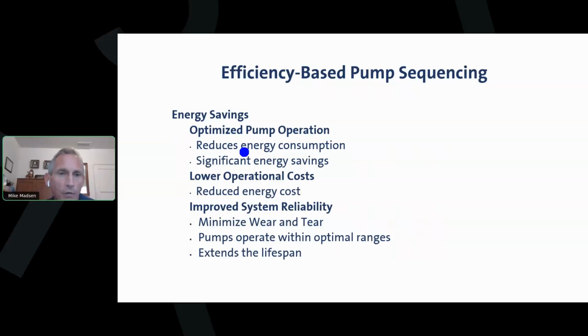So we're going to reduce our overall energy consumption. We're going to rack up significant energy savings and lower our total operating cost. Sort of a side benefit is that as we're running the pumps at slower speed, there's less wear and tear on the equipment also. Running 2 pumps at a slower speed is going to cause less wear and tear on that equipment than running a pump at, let's say, full speed. So there are a lot of benefits to efficiency-based pump sequencing.